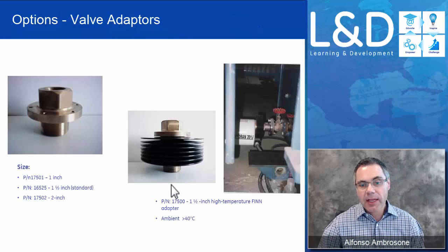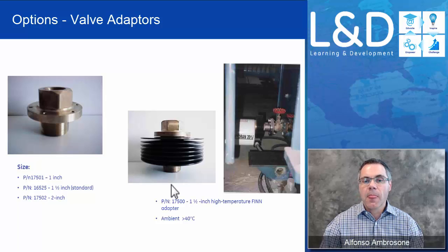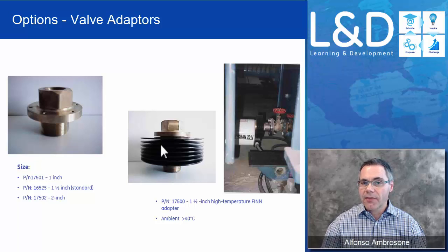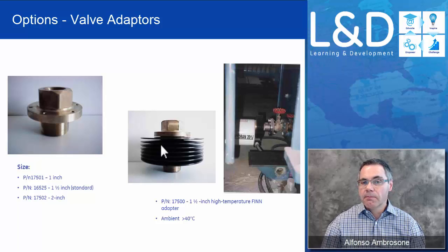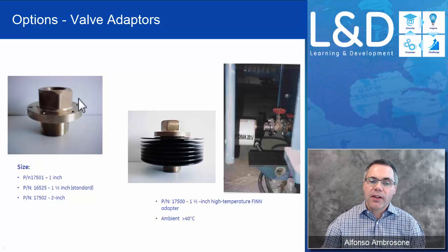One option we have is our heat fin adapter, which is not only for the Ti but also for the M2. We specifically recommend this heat fin adapter in hot tropical areas where we know the oil temperature will be in excess of 50 degrees Celsius. This heat fin adapter will significantly cool down the oil by up to 15 degrees, which will aid and extend the life of the sensor. Under normal operating conditions, the Hydran sensor can last anywhere between five to ten years. However, if operating conditions are abused — specifically regarding oil temperature — the sensor life will be shortened. Using a heat fin adapter is the way to go.